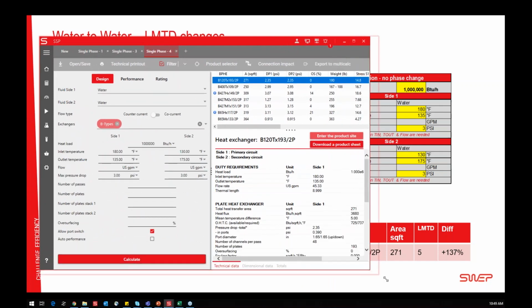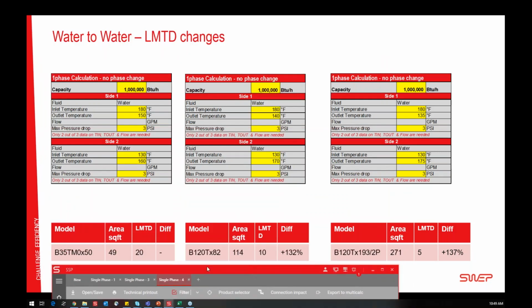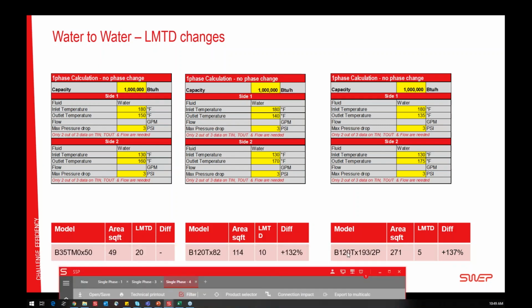And the last one, let's see here, move it over there. The last one is going even closer, 180 to 135 and 175. So we're going only another 5 Fahrenheit closer. Now we're down to LMTD 5, and now we have the same heat exchanger, 120T, as we used before. You can see the 120T with 82 plates, and the 120T with 193 plates. We have more than double the number of plates and went 2-pass. So what we can see here is that the heat transfer surface needed has gone up with the first step 132% and the second step 137%. So it starts to increase rapidly. And I assure you, if you go down toward an LMTD of 2, it will just rise to the highest numbers. But this is quite interesting.